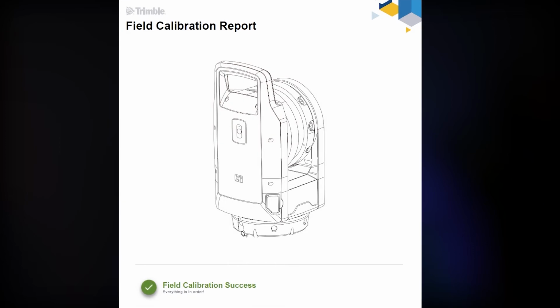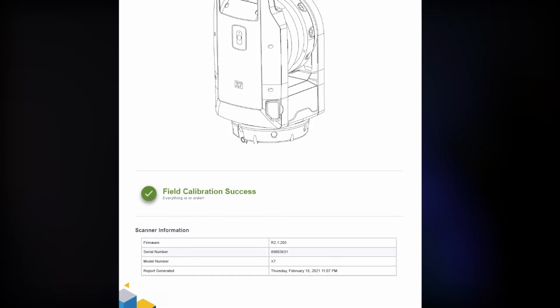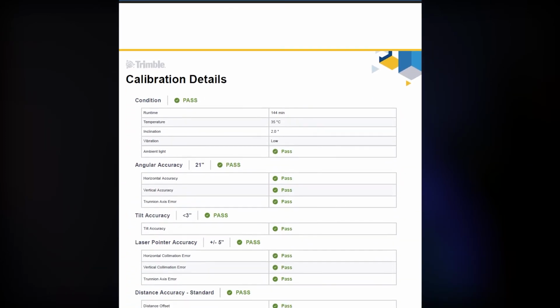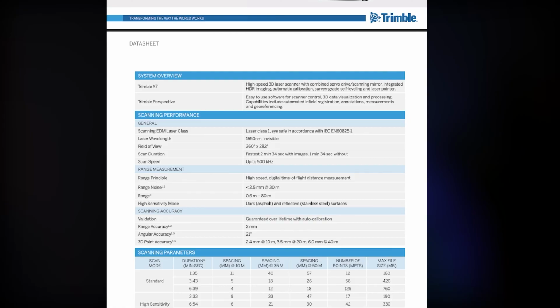And when you're done, you're exporting a calibration report, showing that the measurements taken were within the tolerances set by the manufacturer, without having to send it off for the expensive and time-consuming process of manufacturer calibration and certification. This helps you meet that burden of proof in court, that your instrument was functioning properly and meeting the accuracy specifications established by the manufacturer. Hopefully that answers some of the questions you may have about how laser scanners are calibrated.